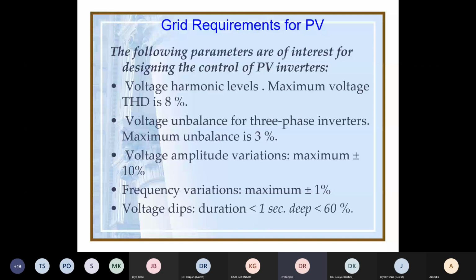As the voltage drops, you can understand that the flywheel starts developing, and the AGC control is actuated, catering to the peak power demand of the load. So there is a supporting system, an inertial supporting system, whereas in a solar system we do not have that. That is why the variation should be maximum 10%. Sometimes we also use storage elements like a battery system, which can provide this support in voltage variation. The second one is frequency variation, which should be maximum 1%.